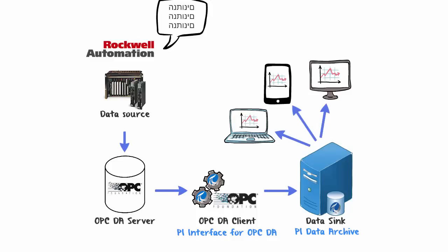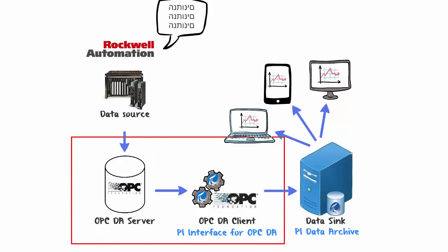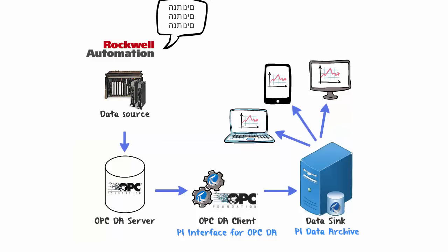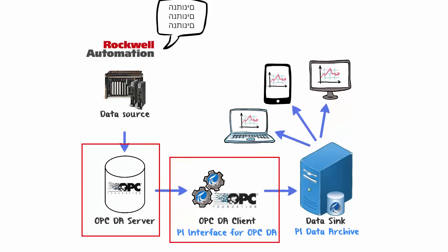At this point you might be wondering where to install these different components. You have a couple of different options, but what we recommend is to install the OPC DA server and the PI Interface for OPC DA on the same node. This greatly facilitates the installation process and also reduces the points of failure since both are on the same node. However, it is possible to install the OPC DA server and the PI Interface for OPC DA on different nodes, but this will require an additional step of configuring DCOM security, so this is important to keep in mind.